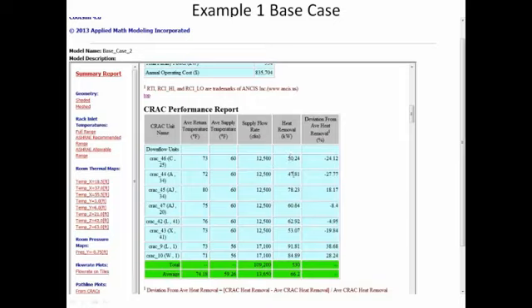We've got one running at 47 here. We've got one running at 62 kW removed of heat. And it has all to do with this return temperature right here. The return temp on this 47 is only 72 degrees. We've got a 12-degree delta between supply and return. And that's largely because this one is running at 12.5 and it's bypassing a bunch of air.